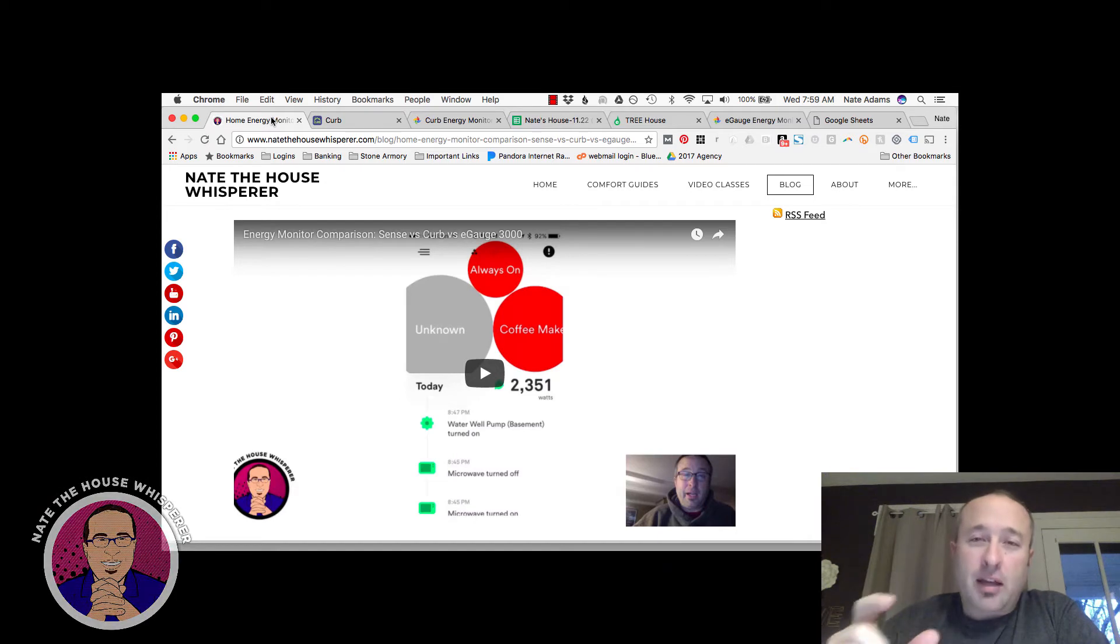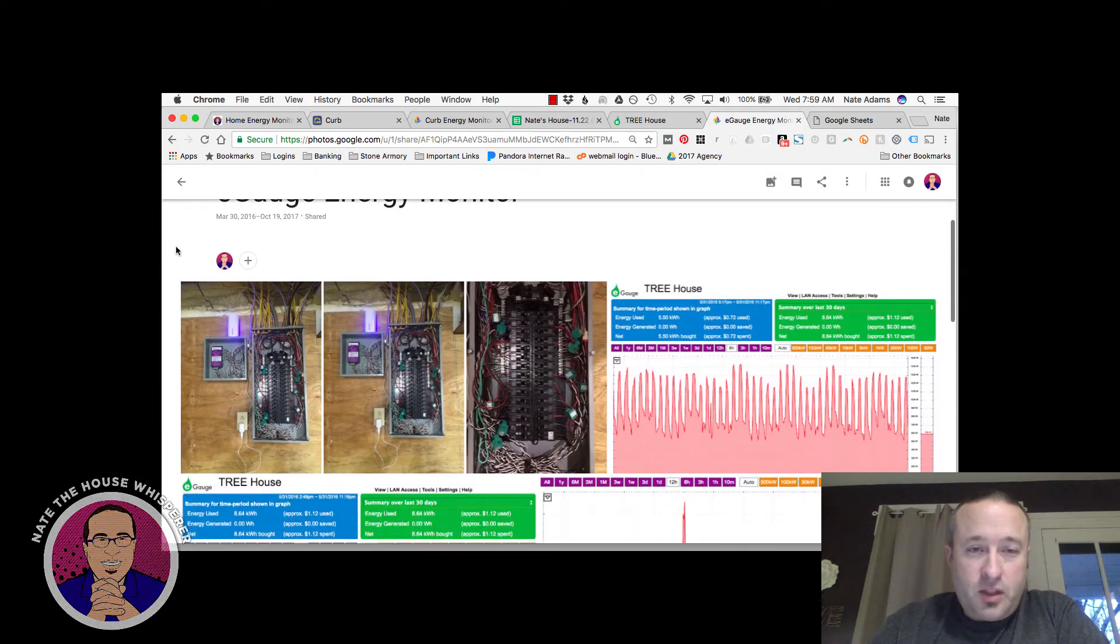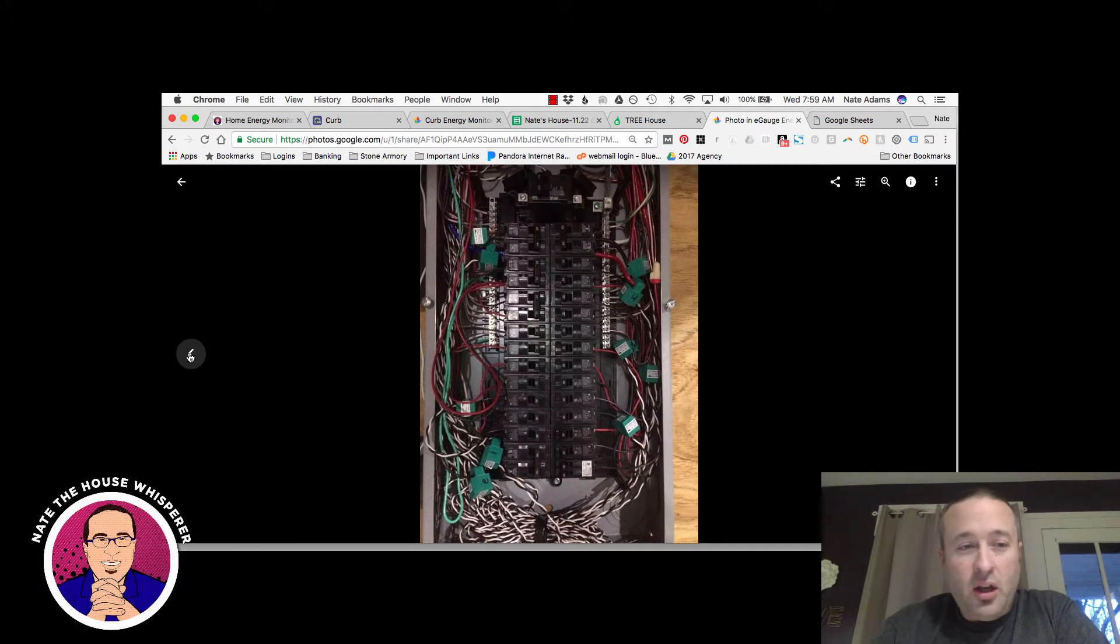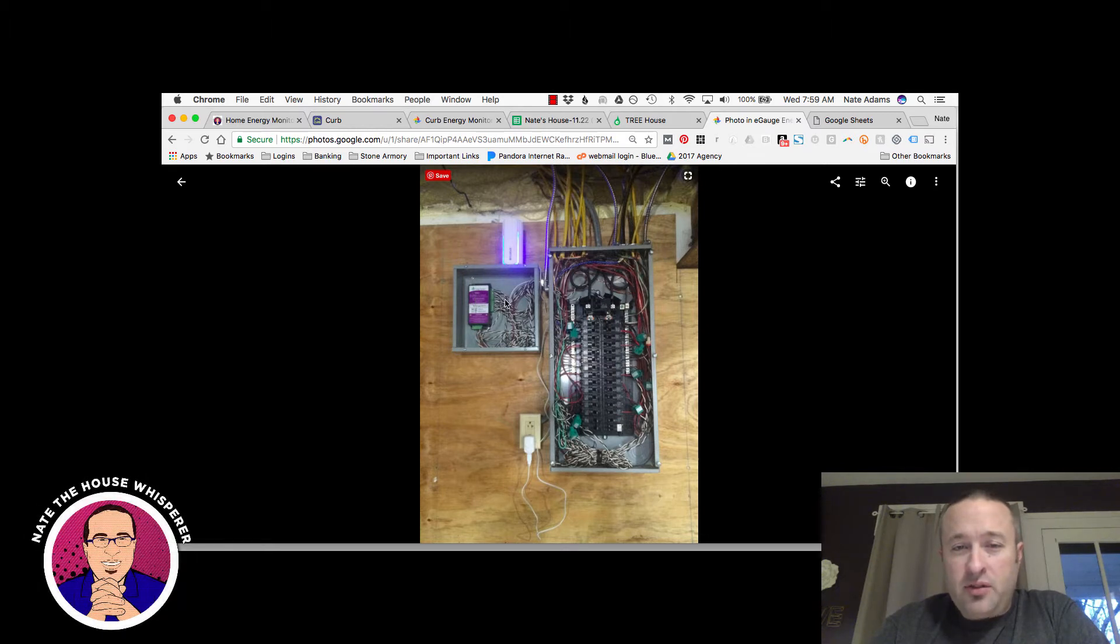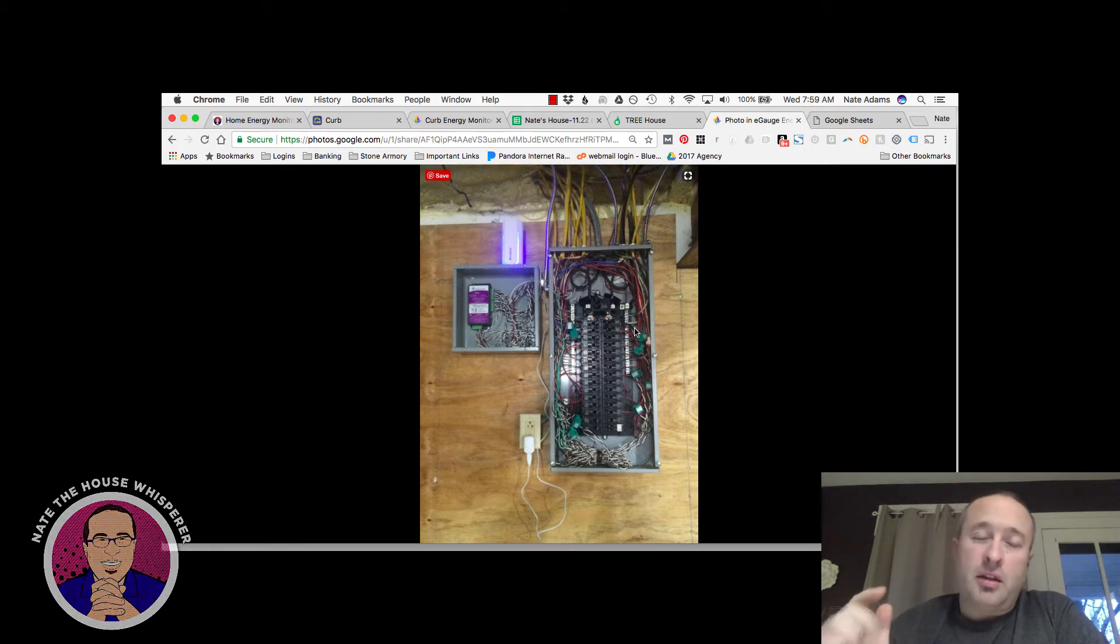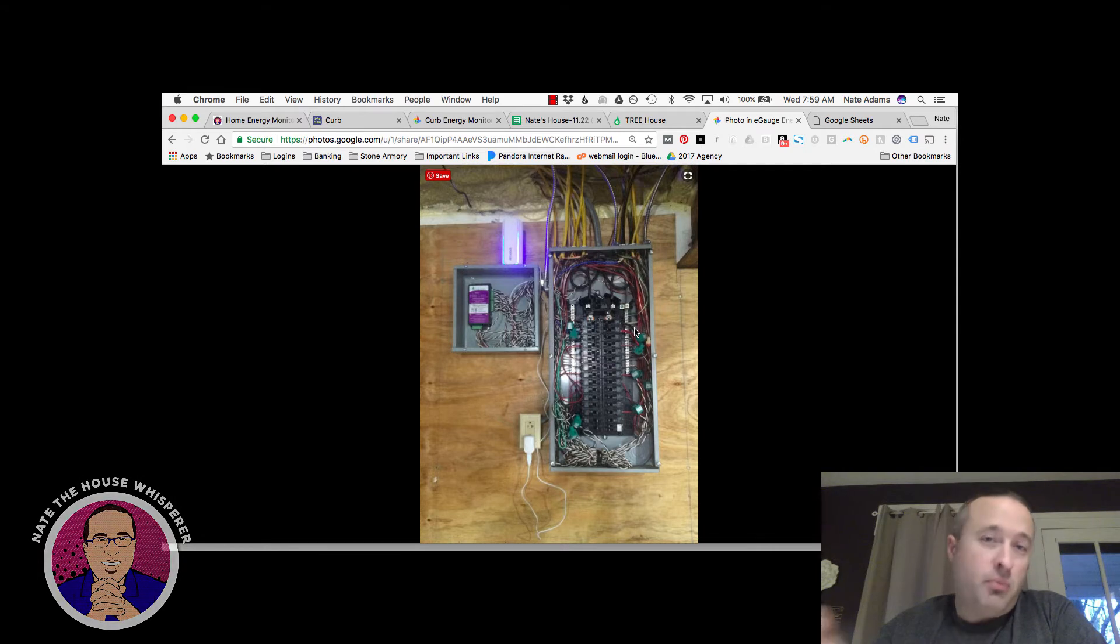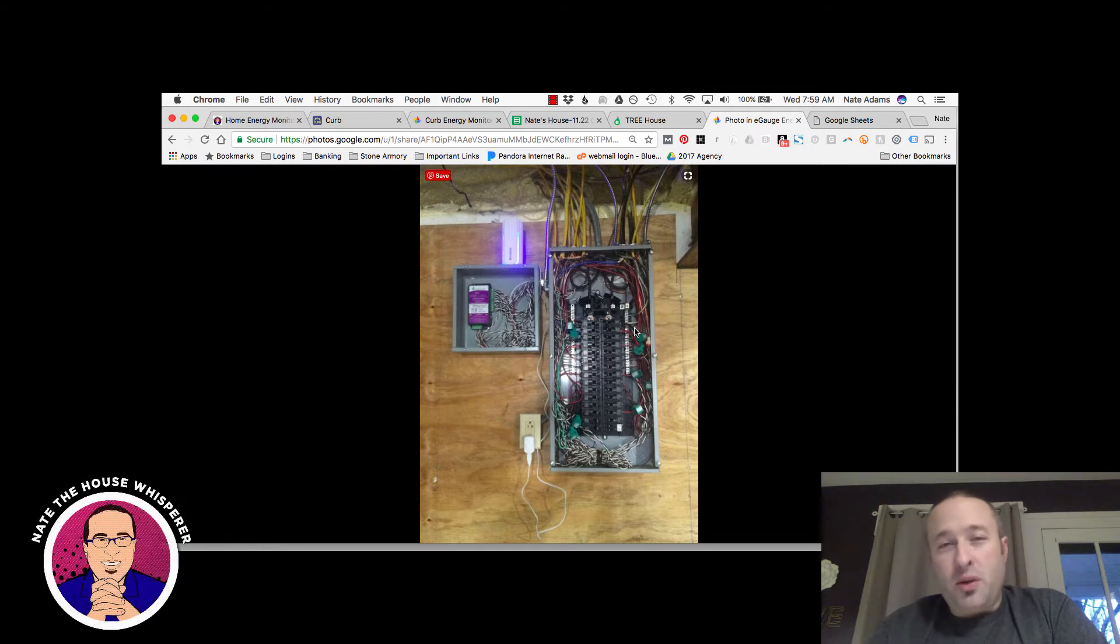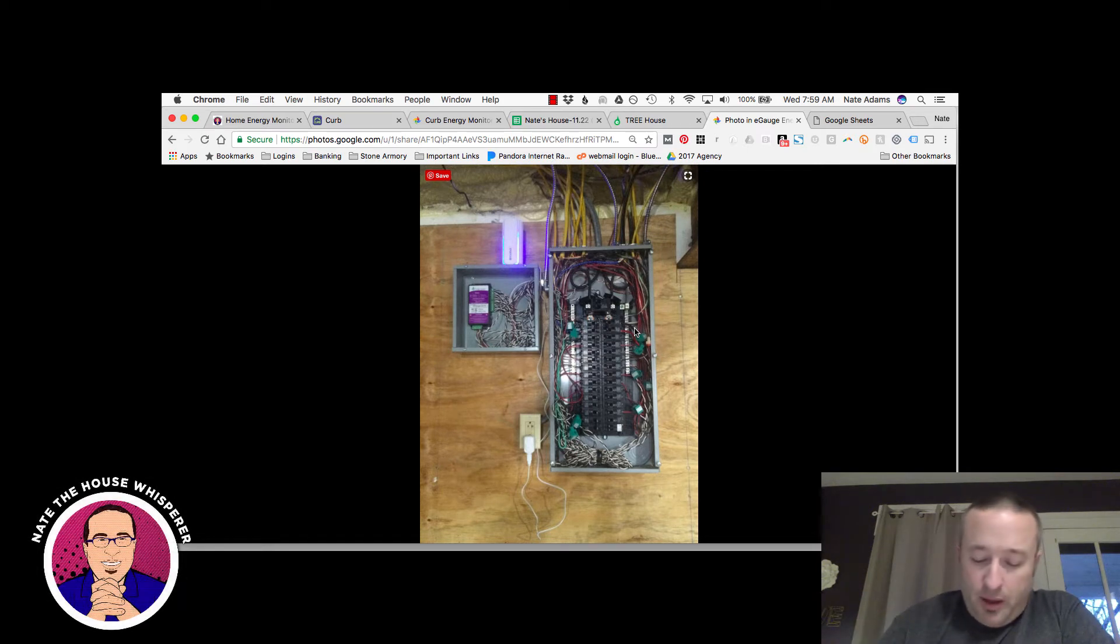All of the type that has individual clamps are tricky. So this is my little photo album. And you can see how much stuff is going on inside of the electric box where this is installed. And this only has, I believe, 12 clamps for it, 12 CT clamps. So this is where the E-Gauge lives. And then all the wires jump over to the main box and pull data from it. So this takes a little time to install. So don't think you're going to do this in an hour. It's probably going to be more. And then you'll likely have to go collect data for a little bit, figure out what you goofed up, and then go and reverse the polarities. Or you may decide you want to monitor something else. For instance, in this house, they're monitoring the stove. But the stove is almost never used. So I would much rather be monitoring another circuit. But that wasn't my call in this case. But plan on it taking some time to put in.